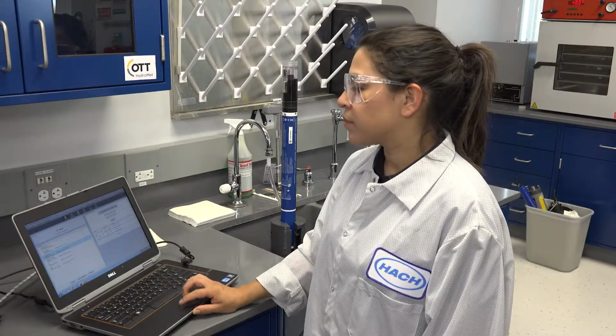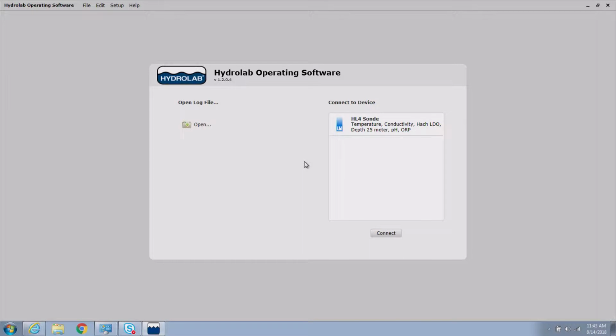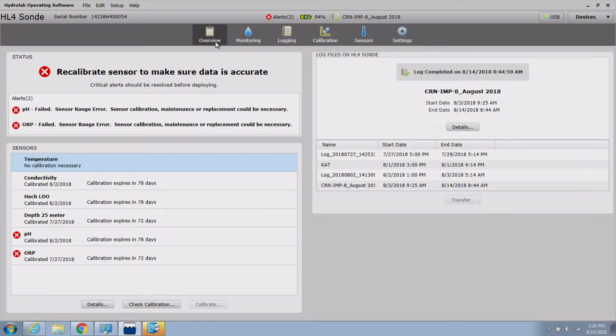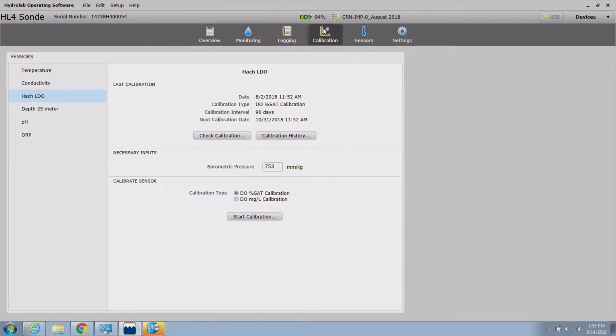Establish a connection to the sonde with the Hydrolab operating software. Select your HL series sonde from the Connect to Device list and click the Connect button to connect to the sonde. When the sonde finishes its initialization, click the Calibration button in the navigation bar, then click LDO in the sensor list on the left-hand side.